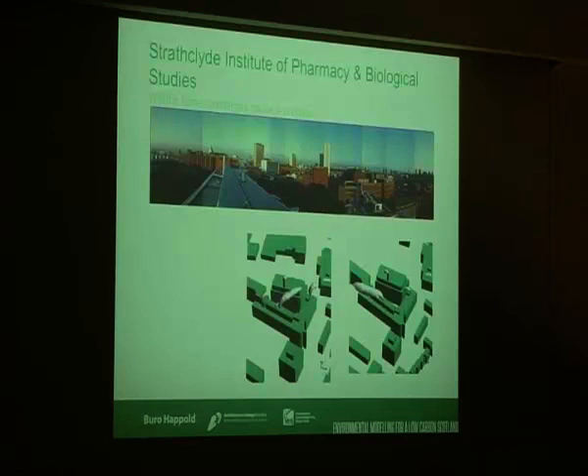What we were able to do by building that model was to actually look at different wind directions. As you see from the plumes there, we got a list of all the contaminants and concentrations that the University were using. We were able to look at that and determine, by the time you reach the buildings and the surroundings, what the concentration was likely to be. The primary thing that came out of this, apart from saying it was safe to build the building, was that there was one chemical they used in this building which we said wasn't safe to use while the new building was being constructed. So over the life of the construction period they didn't use that chemical in the fume cupboards in that building.